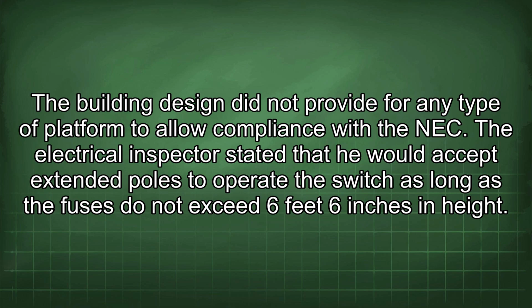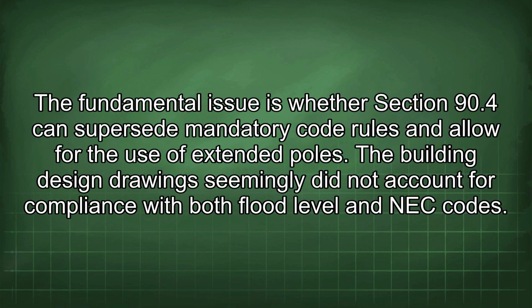The building design did not provide for any type of platform to allow compliance with the NEC. The electrical inspector stated that he would accept extended poles to operate the switch as long as the fuses do not exceed 6 feet 6 inches in height. The fundamental issue is whether Section 90.4 can supersede mandatory code rules and allow for the use of extended poles.